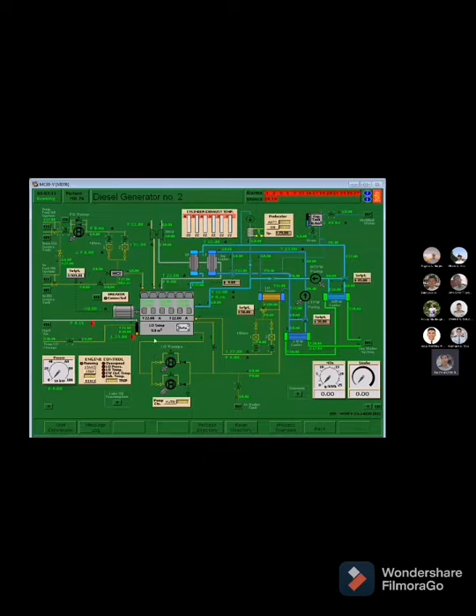Let's light up the second diesel generator. Check the lube oil sump tank level. Open the lube oil filter number 1. Open the lube oil priming pump. Open the diesel oil filter number 1 and the shut off valve for diesel oil. Put the preheater to on. Then let's wait for the sump pump. Then let's turn on the hand pump for faster feed. And let's wait until 20 bars.